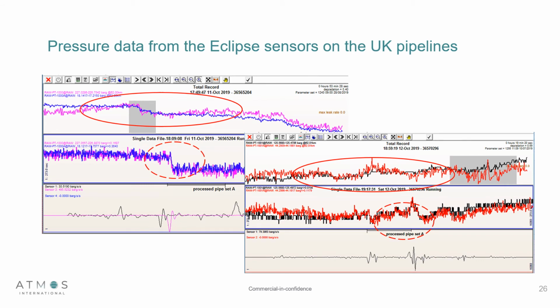So what I wanted to show you here is pressure data from a non-intrusive Eclipse unit and pressure from an intrusive PT on the same pipeline. In the first screenshot in the top left, the pink is showing the non-intrusive pressure, and the blue is showing the intrusive PT. What I want to highlight here is the small change in pressure that is actually being detected. This small operational change equates to 0.3 bar of change. And as you can see in the top trend and in this middle trend, both the non-intrusive pressure and intrusive pressure are coupled together and follow a very, very similar pattern.